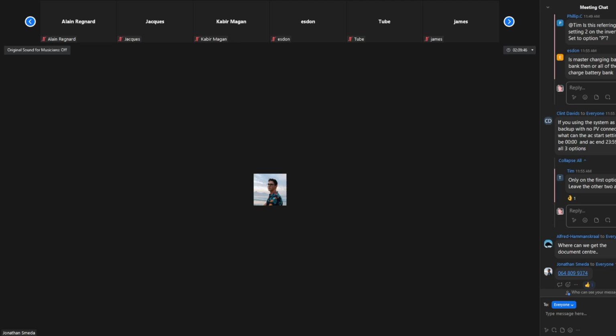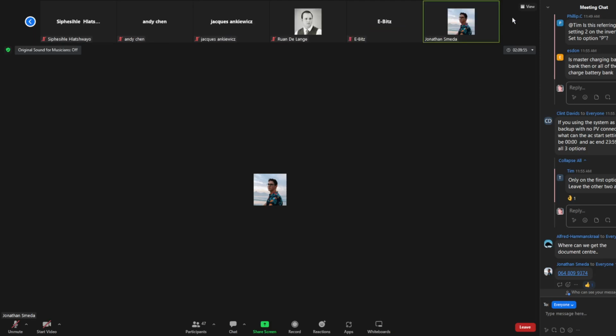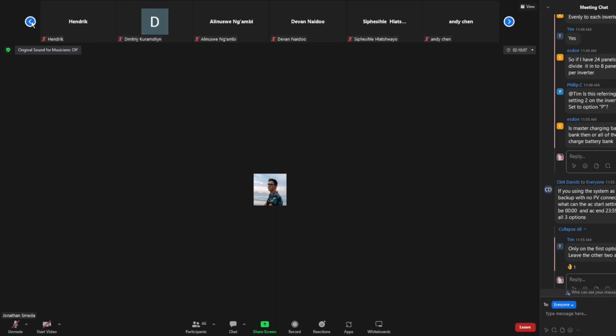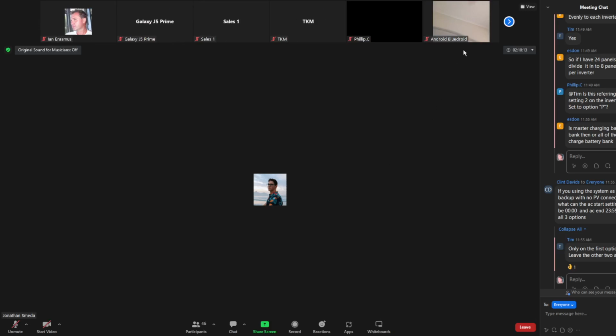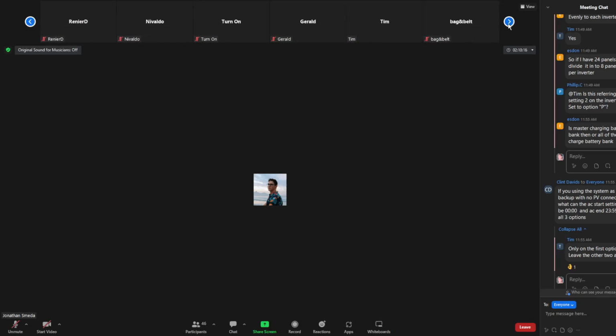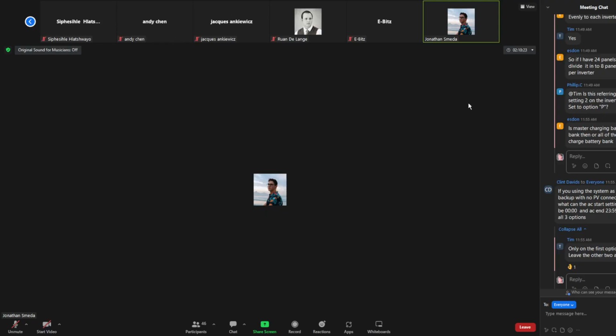Okay, can I show you something after the seminar on the Luxpower inverter? In most cases, clients aren't saving the settings properly. When you go into the Luxpower and try to program the settings, you hold the enter button for 2 to 3 seconds until it starts beeping fast, then you're in the settings page. Select the setting you want, change it, but if you press the return button instead of enter, it doesn't save. You have to select what you want and press enter, cycling through all the options, and only when it exits the setting is it saved.